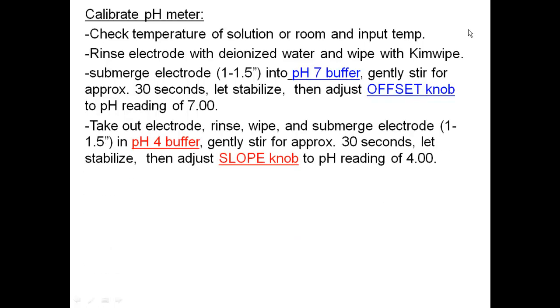Then we're going to take the electrode out, rinse it, then submerge it about an inch or so into the pH 4 buffer. Gently stir for about 30 seconds. Then we use the slope knob to adjust to 4. So we calibrate the instrument of what 7 is and what 4 is. Then you place the electrode in tap water until you're ready to use it.